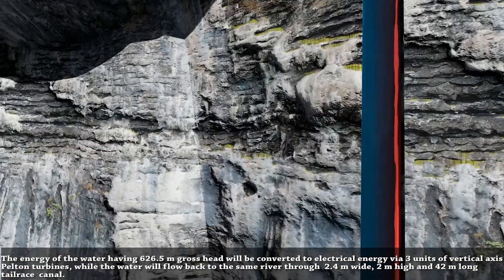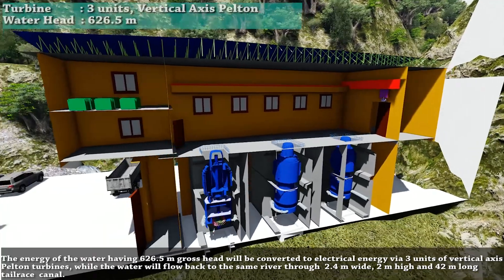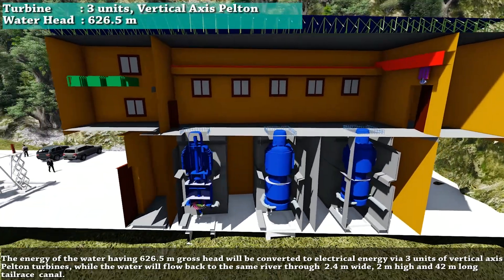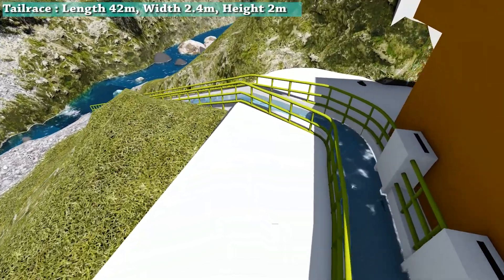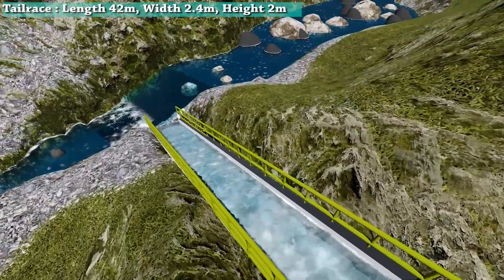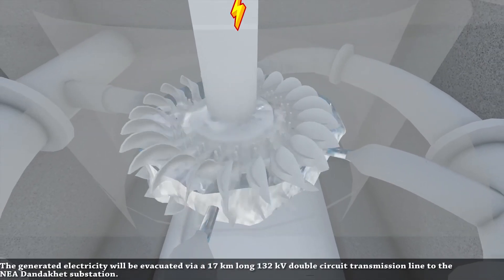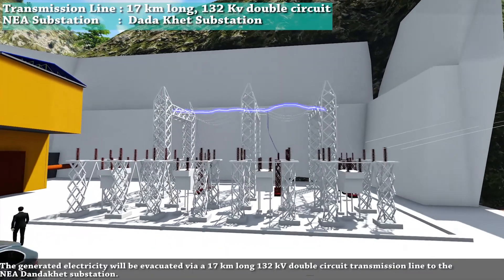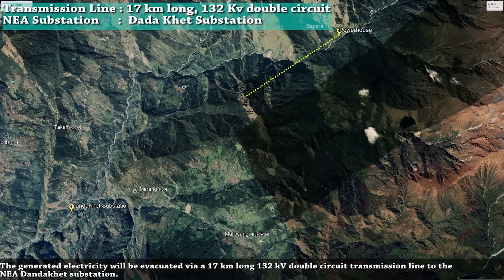The energy of the water, having a 626.5-meter gross head, will be converted into electrical energy via 3 units of vertical axis Pelton turbines, while the water will flow back to the same river through a 2.4-meter wide, 2-meter high, and 42-meter long tailrace canal. The generated electricity will be evacuated via a 17-kilometer long, 132-kilovolt double-circuit transmission line to the NEA Dandakhet substation.